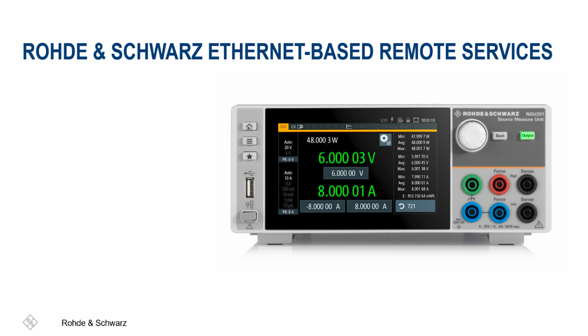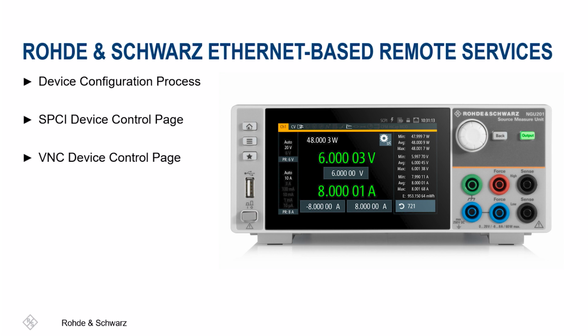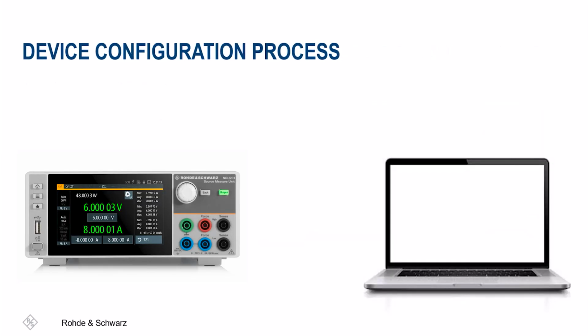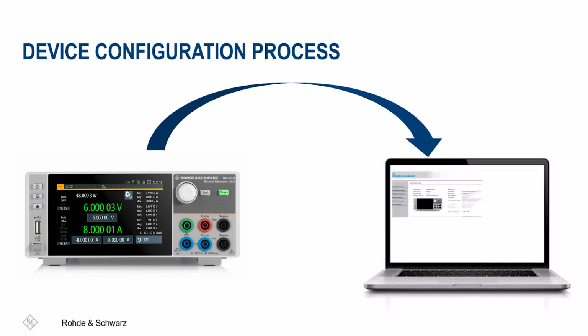power supply. These services are comprised of an instrument webpage, VNC remote control, and FTP file transfer between the instrument and a remote computer. To access an instrument's GUI remotely, an Ethernet connection must be established between the instrument and computer. When the instrument's IP address is entered in a web browser, the instrument's web page opens.